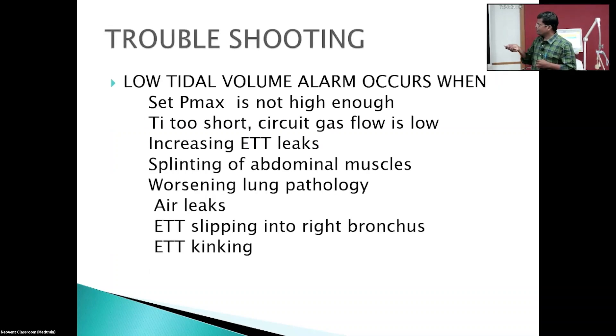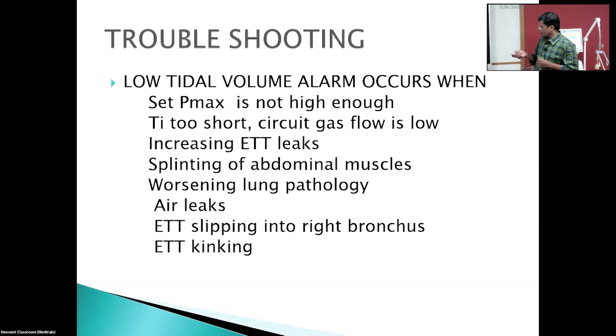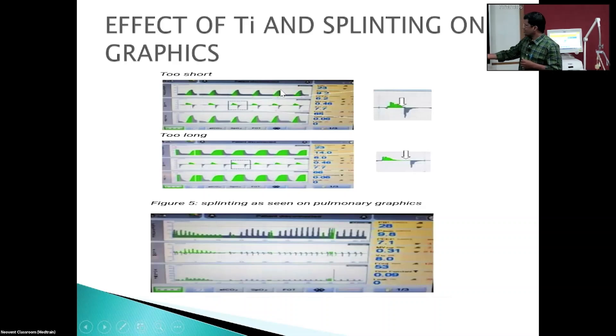Troubleshooting: a low tidal volume alarm occurs when P-max is not high enough, Ti and gas flow are low, there is an increasing ET tube leak, the baby is crying or splinting abdominal muscles, or there is worsening lung pathology or air leak. Monitor for ET tube kinking or slipping into the right bronchus. The graphs shown illustrate: short Ti with a small unsustained peak, too long Ti, and a baby splinting generating higher tidal volume.